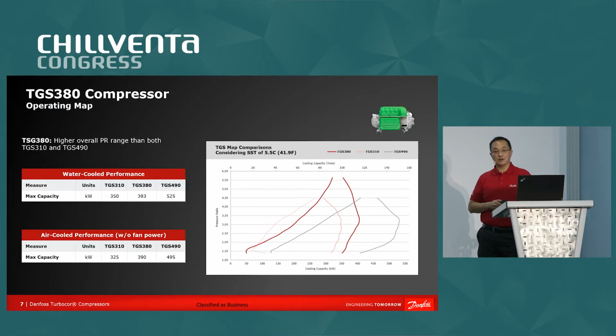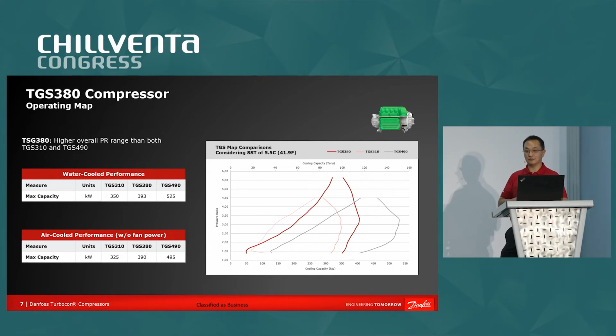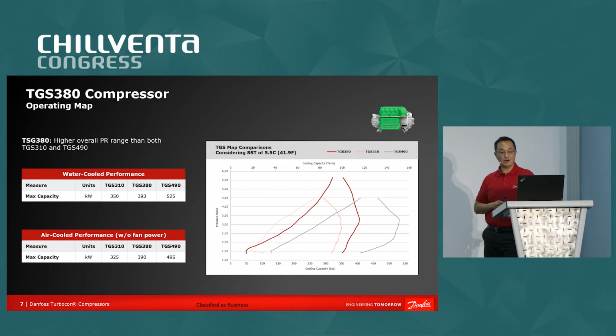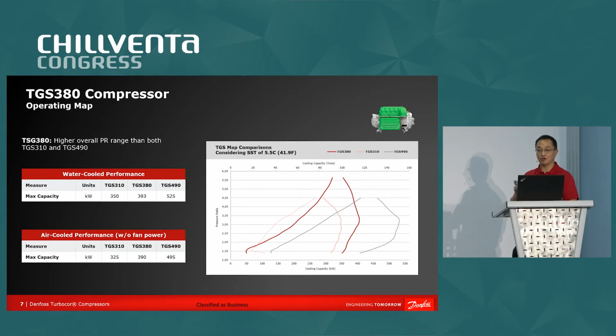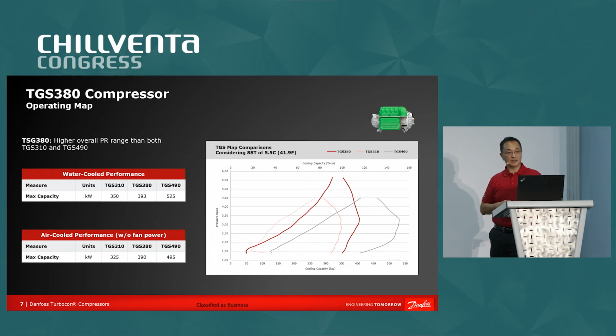So this specific compressor fits very well within our compressor portfolio. The TGS 380 is a nominal 380 kilowatt capacity compressor. So you can see how it fits in between our TGS 310 compressor and our TGS 490 compressor. So it fills in a nice capacity gap in between those two models. And as you can see from the dark red line right up on the top there, the top of the curve indicates that it can achieve a higher pressure ratio, 5.7. So that allows for operation in the applications I mentioned earlier, heating as well as high saturated suction temperature or data center cooling applications.